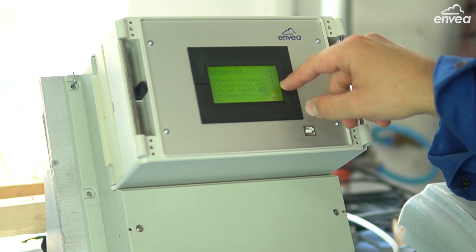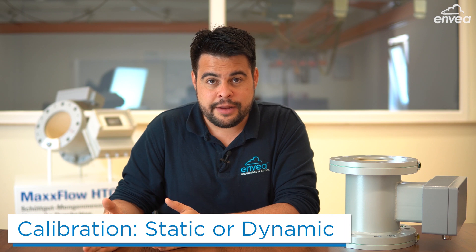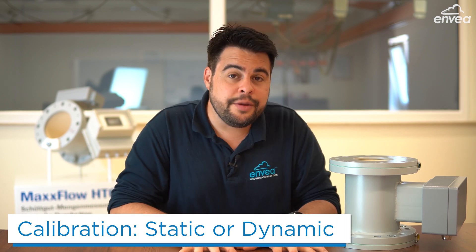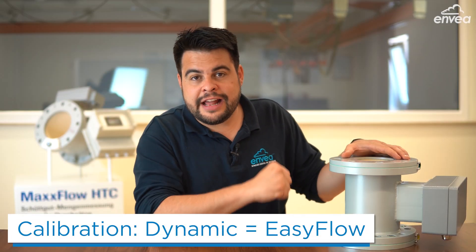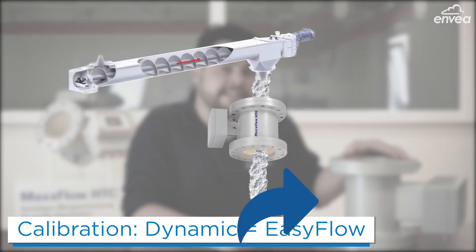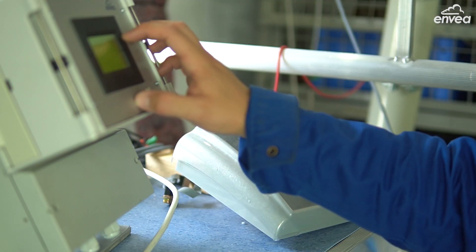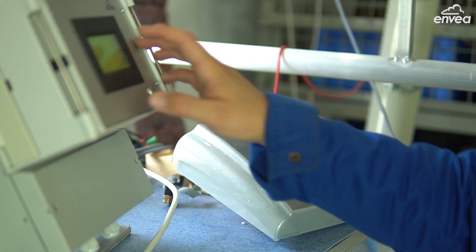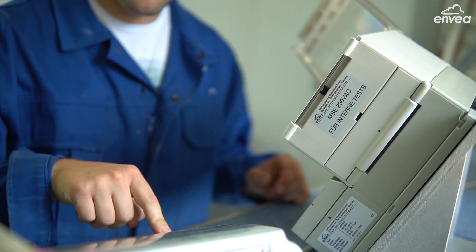Calibration — something easy to do with MaxxFlow. We have two options available: static and dynamic calibration. For the static calibration, the sensor is filled to 100% and using the bulk density information, the mass flow can be calibrated. For the dynamic calibration — we call it easy flow calibration — we convey material through the sensor, get a sample, weigh the sample, and then reference the sample with the sensor readings. And that's all. With this calibration we can achieve very good results.